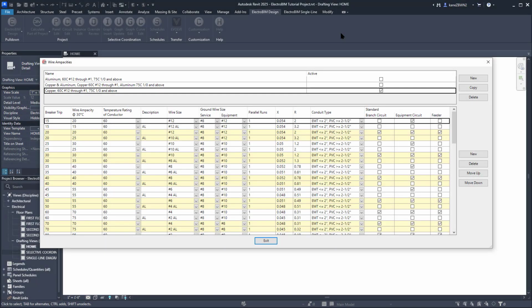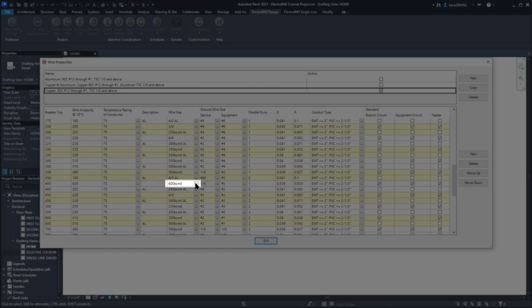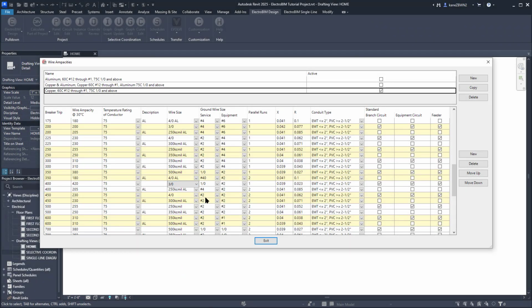It has enough controls defined to be usable out of the box, but the sizing table is designed to be modified to fit your company's standards. One popular change is at the 400 amp level, where instead of using 600 kcmil for the conductors, they'll use two runs of 3/0.